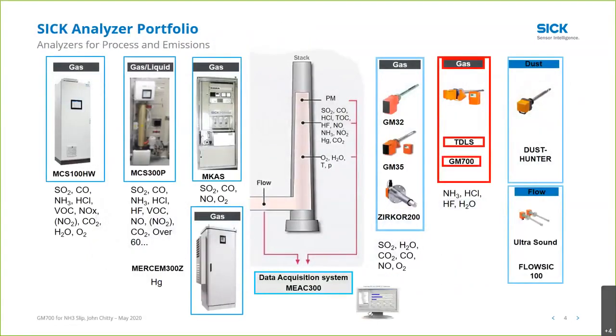For today, we're discussing analyzers. This slide shows the breadth of the analytical product line. SICK offers extractive analyzers. This is the MCS100E being shown. This is a hot wet extractive CEM system. We probably have in excess of 3,000 of these installed worldwide. Next to this, you see the MCS300P. It's a raw gas analyzer, still a hot wet analyzer, mainly for process type applications. And then we have the standard continuous gas analyzers, cold dry extractive CEM systems, also used in process applications where there's a clean, dry gas as opposed to the wet gases in these.